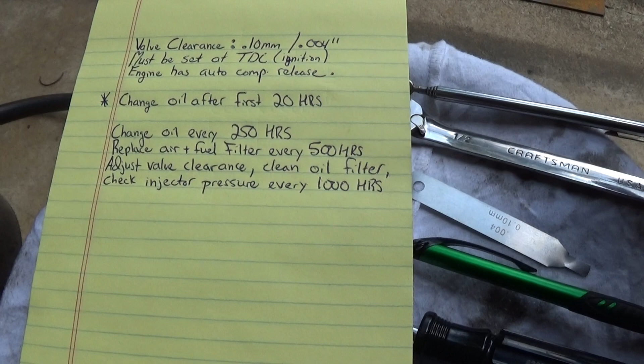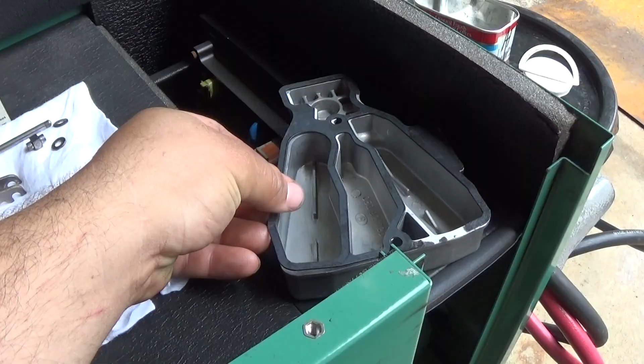We're going to put it back together and adjust the clearances. I'm going to reuse this valve cover gasket for right now, just put a little bit of silicone around it to get it running and tested, and see if this thing's worth putting any effort into as a usable generator. I'm going to reassemble those rocker arms and get them adjusted. I'll save you having to watch me working in that little hole, and we'll come back when I've got it put back together.